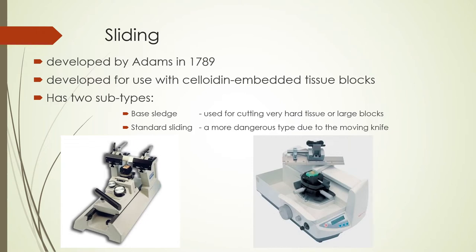The standard sliding microtome garnered the nickname of the most dangerous type due to the moving knife. In most microtomes, the moving part is the tissue block — as in the rotary and rocking microtomes. But in the standard sliding microtome, the knife itself is moving. So when you're cutting, it is very dangerous because it might cut your finger.